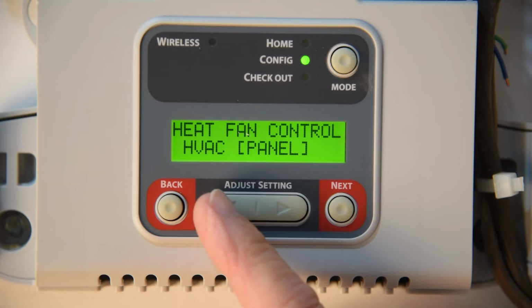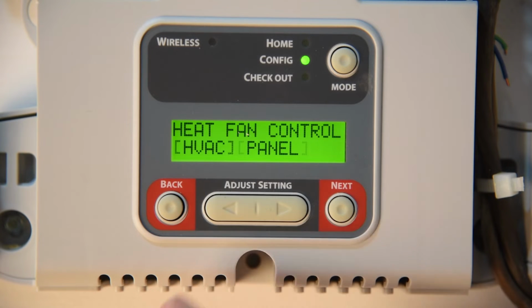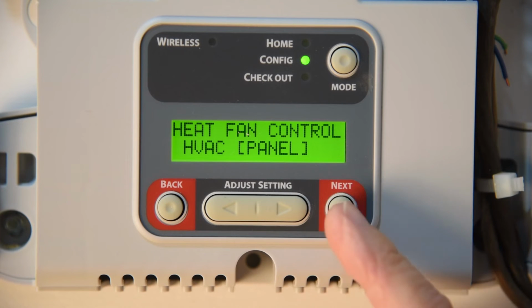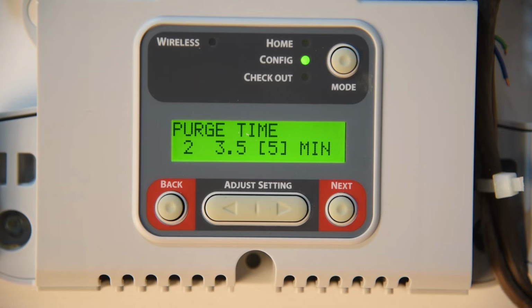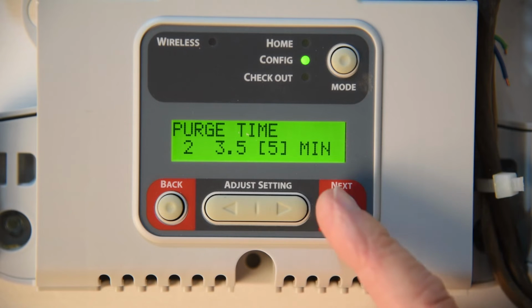Now, on the heat fan control, I can have the equipment or the panel control it. I'm going to let the panel control it. I bought a nice panel. I want it to do what it's supposed to do. Okay, your purge time. That is to clear out the ducts after you've been heating or cooling. You can go 2 minutes, 3.5 minutes, or 5 minutes. I use 5 minutes. My reasoning is I want to mix the air through the house, do a little bit extra filtration by running air through the furnace. So I use 5 minutes. You could use another one.